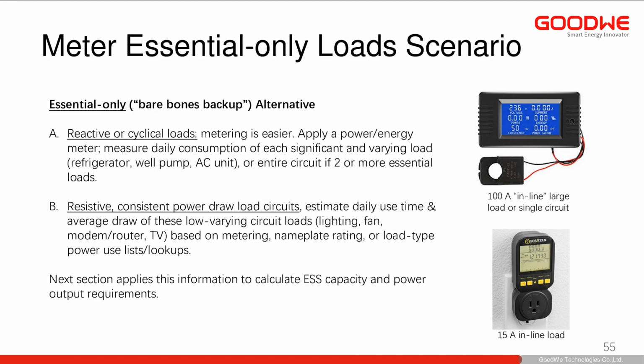This is really useful for those reactive loads that are pretty hard to get a good gauge on their usage, either because they cycle a lot or they have this great inrush current that's hard to determine. You can look at consumption over time with devices like you see on the right. They may even be good at picking up the inrush current. However, I would have a quality clamp meter and set it to max and get the RMS value, the true RMS value, or know if it's a peak value from your Fluke device or whatever you're using. So you can get the inrush current by starting up that AC compressor and having your clamp meter over it.